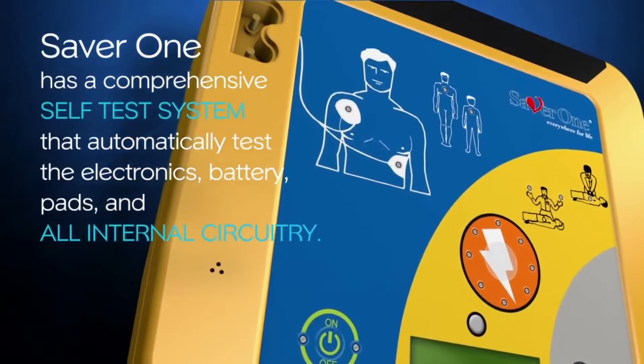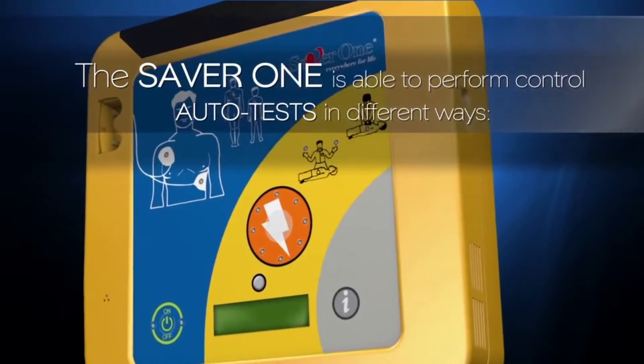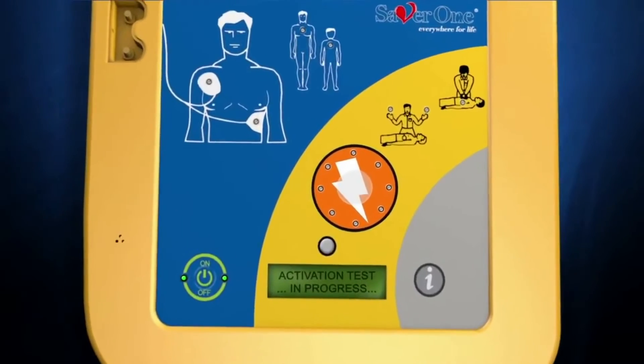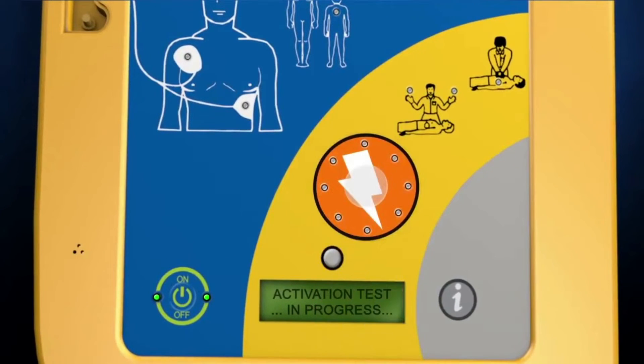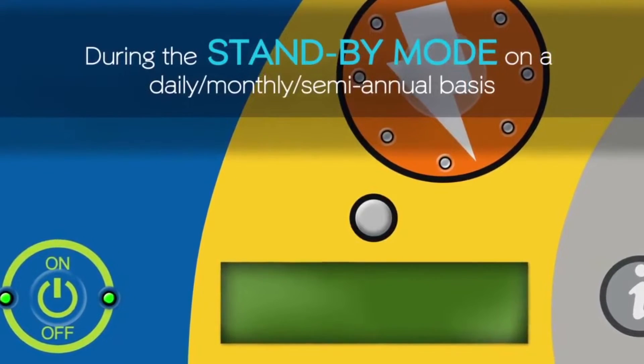The Saver One performs automatic control tests in different ways during standby mode: on a daily, monthly, and semi-annual basis, and whenever you insert a battery. During the activation test, the Saver One performs a diagnostic test, activating voice instructions saying 'Testing device — press shock button.' If the test is successful, 'Activation test succeeded' will be displayed on the mini LCD. This test also verifies the functionality of the keyboard buttons and requires your assistance.